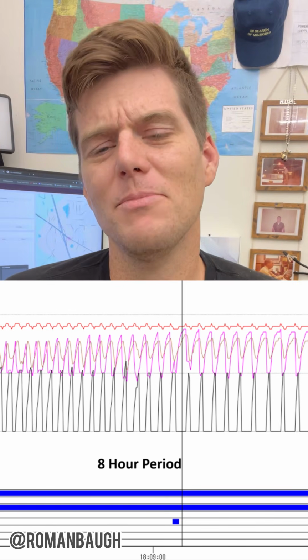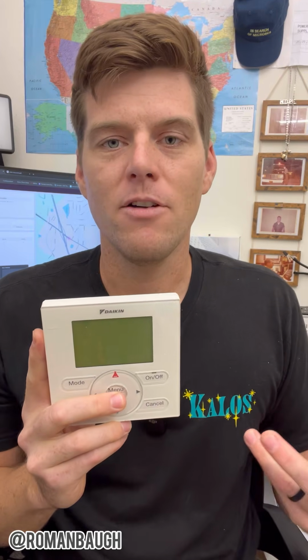What would cause something like this now that you know what it looks like? Setting incorrect field settings on the indoor BRC controller or whatever controller your VRF system might have. Remember, there's a thermistor here, there's a thermistor in the return air, and sometimes it can do an average between that one and this one based upon the field settings that you select and how you commission your unit.